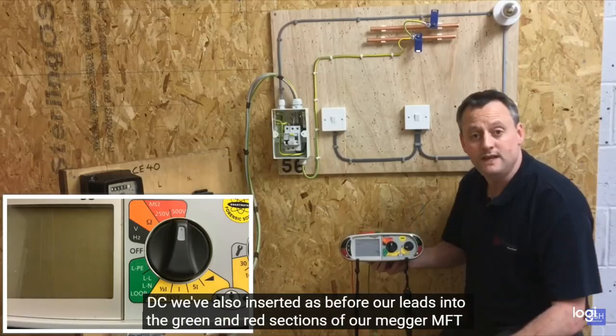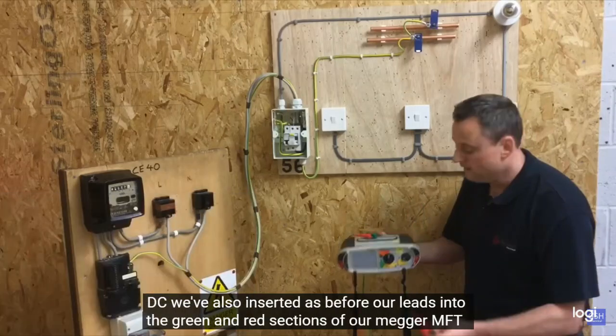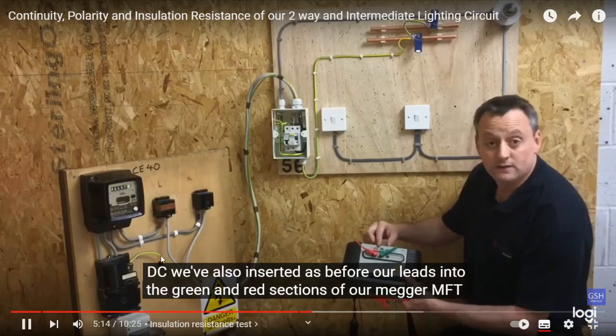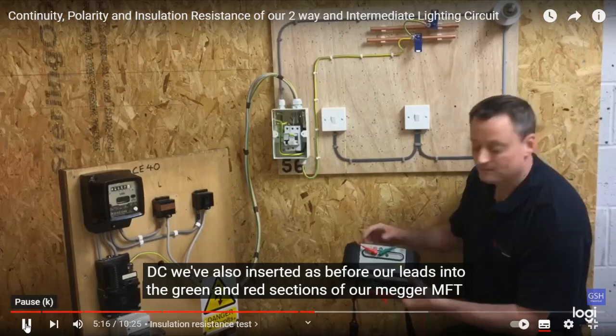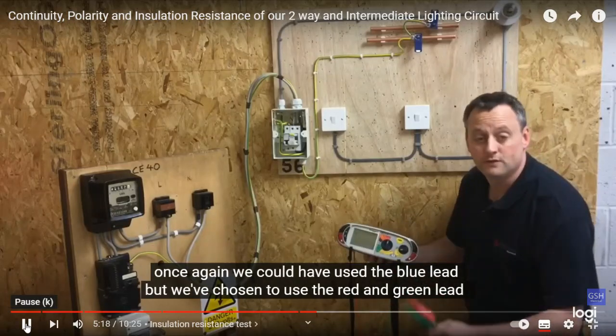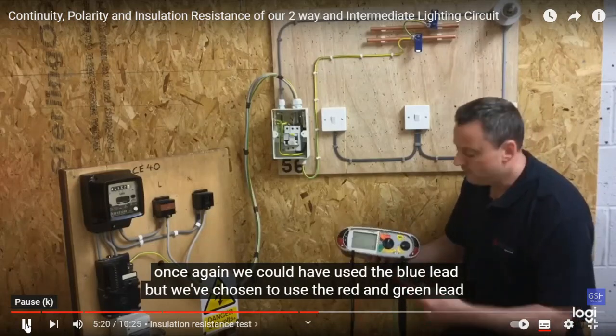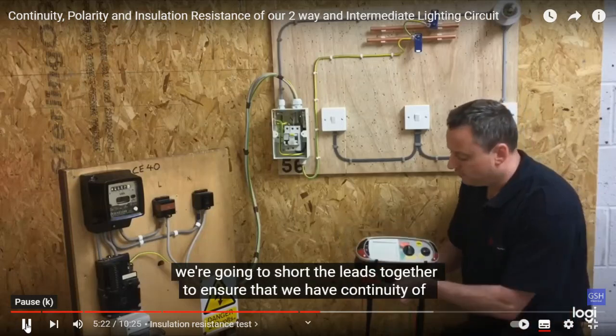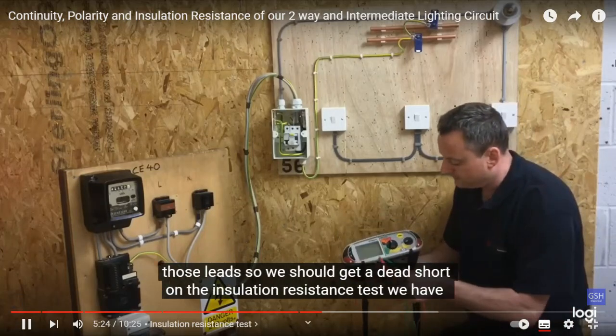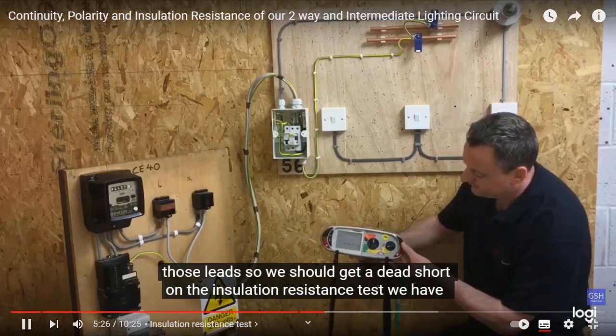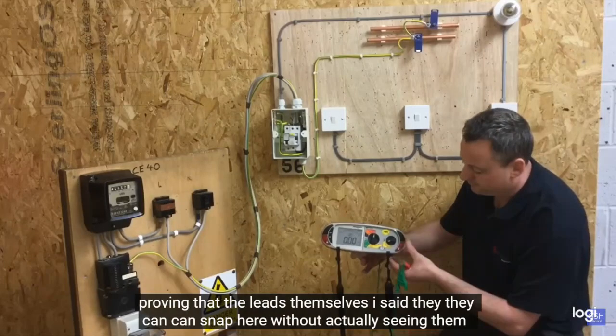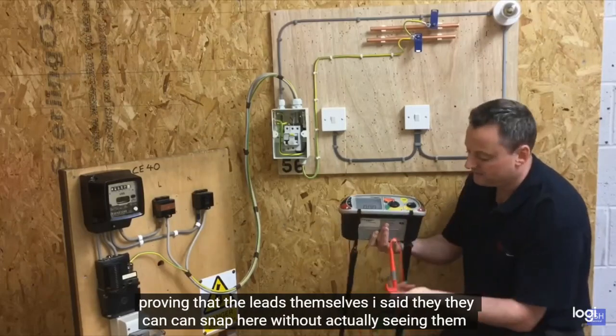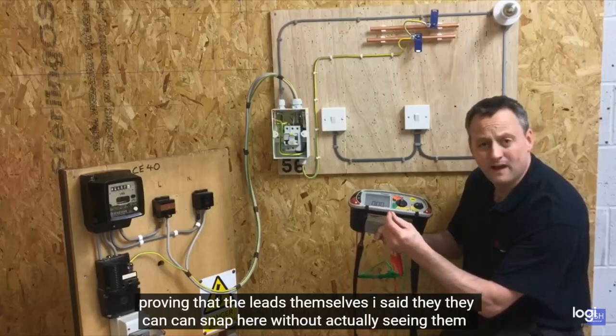We're going to short the leads together to ensure that we have continuity of those leads, so we should get a dead short on the insulation resistance test. This proves that the leads themselves, and as I said, they can snap without actually seeing them physically snap, they can become disconnected. So we've proved we have continuity of our leads by shorting them together, and we're almost ready to start our insulation resistance test.